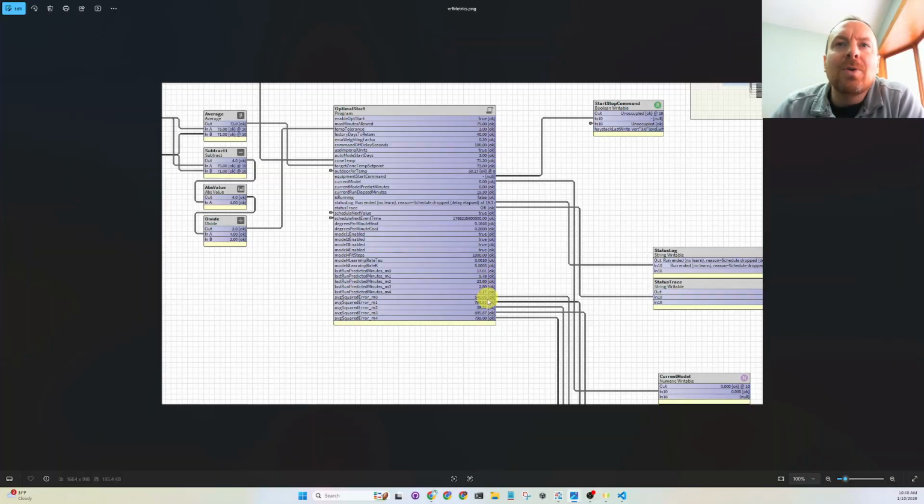And what I wanted to do was, there's actually, I'll show you in a second, history days to retain. So this actually runs, every time the block runs, which we've been talking about in the previous videos. We snapshot the delta temperature, which is the zone temp and the target zone set point. And I have a tolerance built into that, and the outside air temp. And then there's a unit of time in minutes. So that's how we're running all these different math models across that.